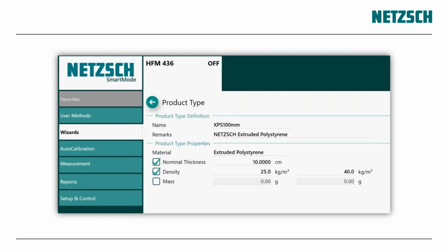enter the product type XPS 100 millimeter into our product type database. You can also enter a nominal thickness and a nominal density range. So you can store all your products that you quality control in your daily business in our database. And when you start a measurement on a sample, which could be a sliced 100 millimeter product, you can dedicate it to the product type 100 millimeter.